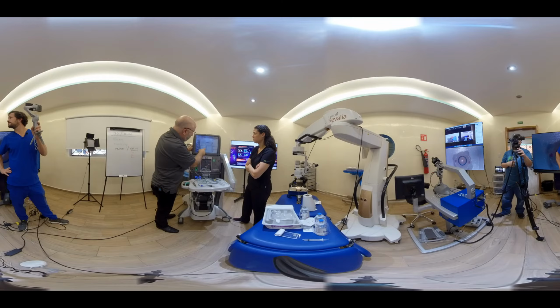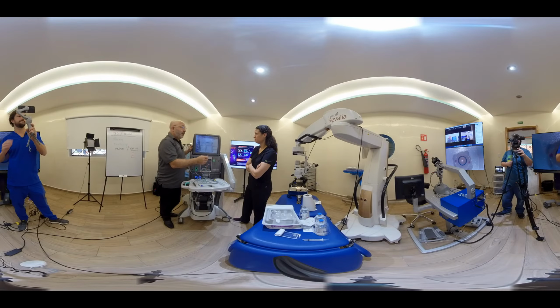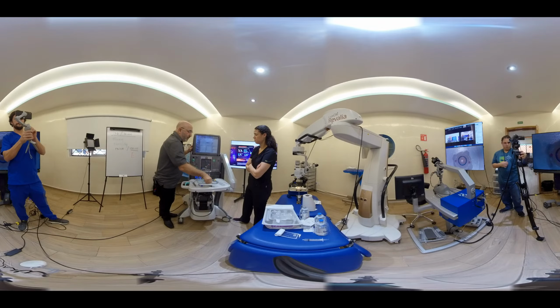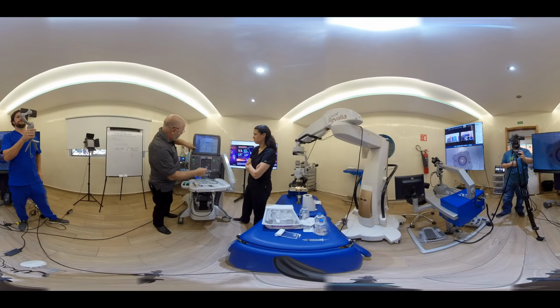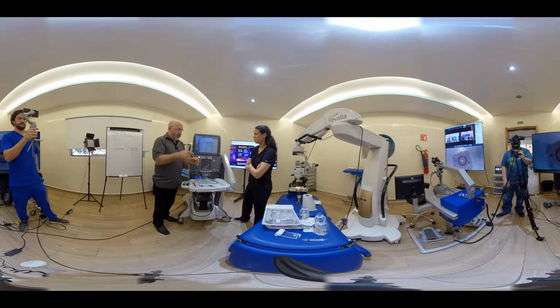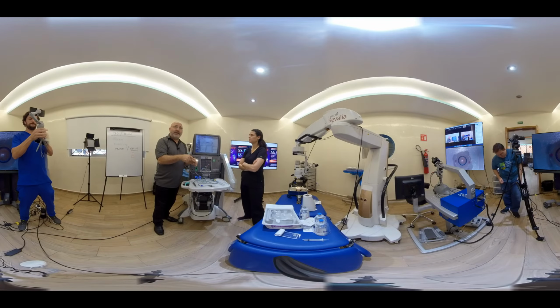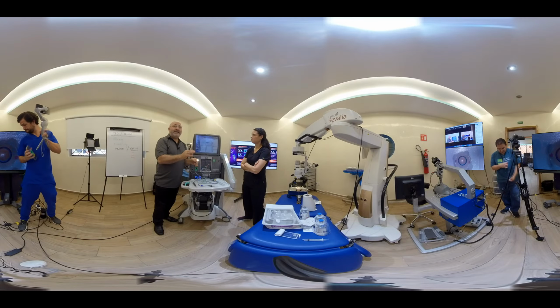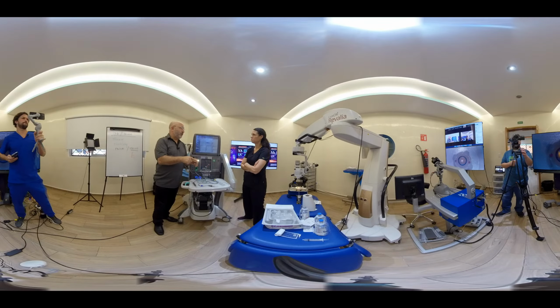So here you'll see 27 gauge plus. The RFID reads what it is and tells the machine, hey, I'm a 27 gauge, straight, not wide angle, light pipe. Please load the parameters for this light pipe so that when I turn on the light pipe, what I have in terms of illumination is 8 to 10 lumens at the tip.